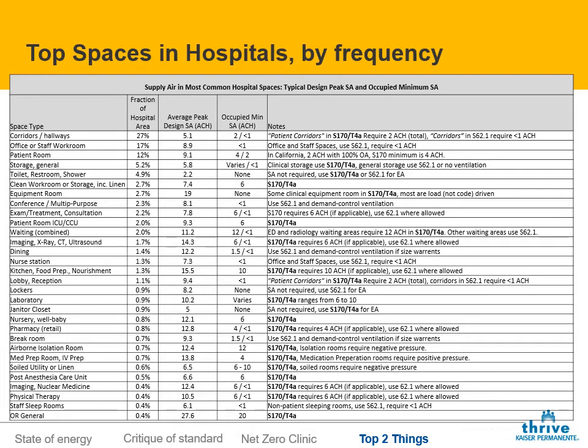First off, remember in the beginning that I mentioned that isolation rooms and operating rooms and protective environments and compounding pharmacies are less than 5% of a hospital's footprint. And you can see that. You can totally see that in the data, right? Operating rooms are way down on the list. Isolation rooms way down on the list. They're actually less than 2% of the footprint of hospitals.